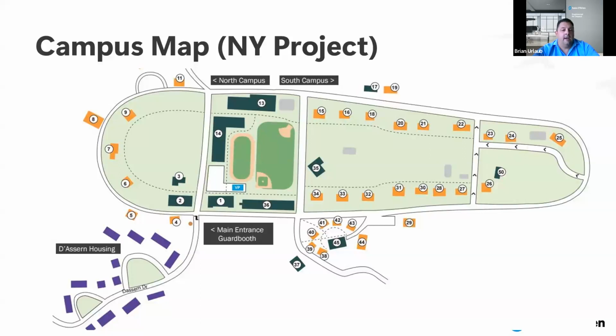You basically had bedrock at surface or within 10 feet of surface, so trenching and installing piping externally for a district system is very challenging. The single pipe ambient approach made the most sense because we could reduce costs in piping and trenching. We also wanted to thermally connect all these buildings because there's a lot of diversity here.